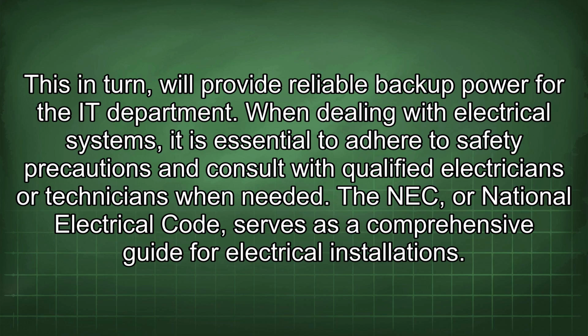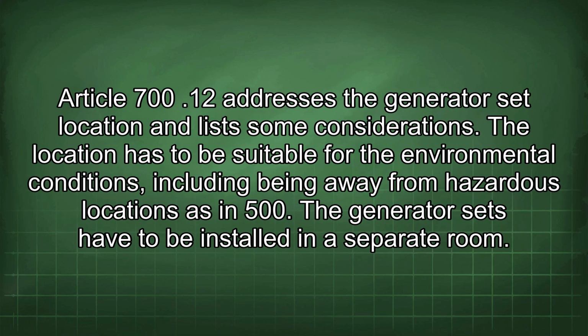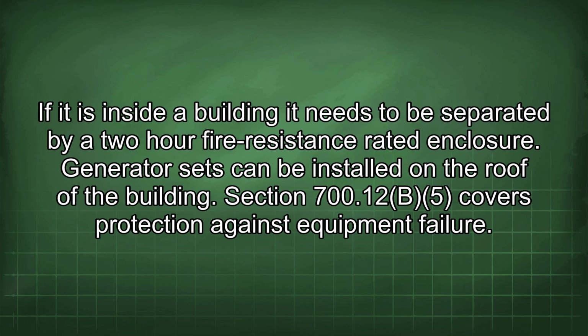When dealing with electrical systems, it is essential to adhere to safety precautions and consult with qualified electricians or technicians when needed. The NEC, or National Electrical Code, serves as a comprehensive guide for electrical installations. Article 700.12 addresses the generator set location and lists some considerations. The location has to be suitable for the environmental conditions, including being away from hazardous locations as in 500. The generator sets have to be installed in a separate room. If it is inside a building, it needs to be separated by a 2-hour fire resistance rated enclosure. Generator sets can be installed on the roof of the building.